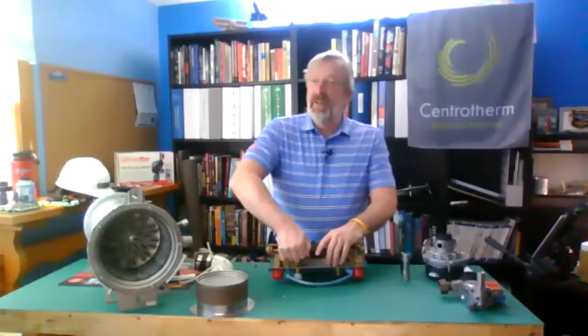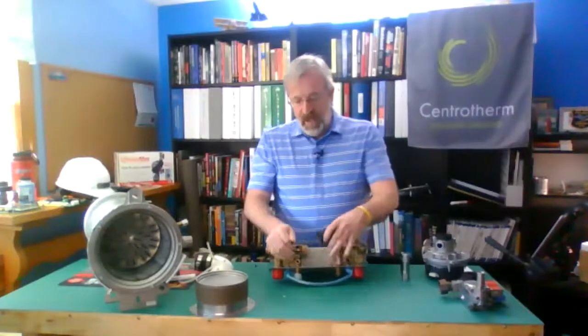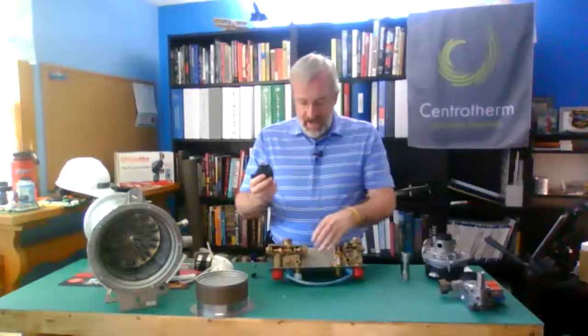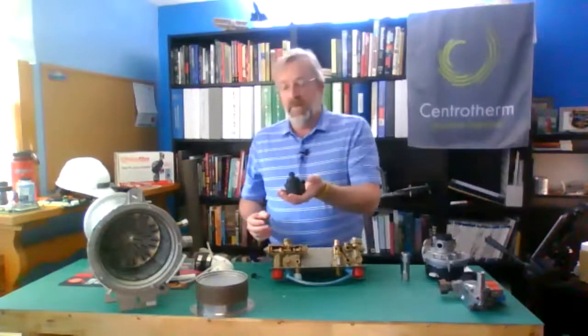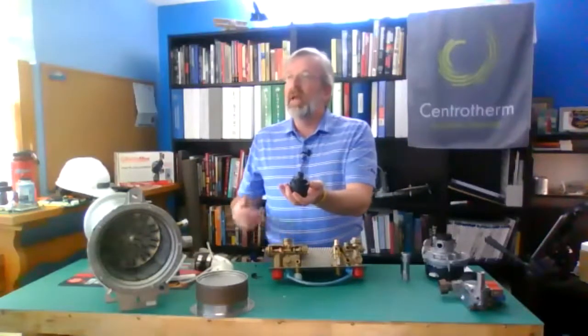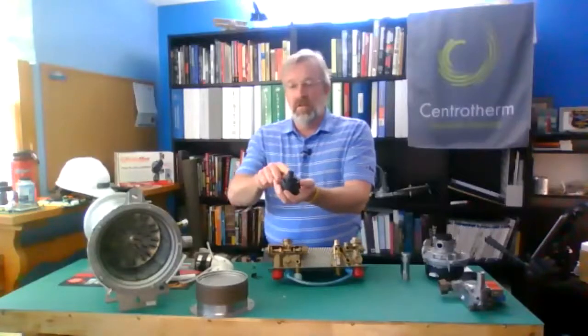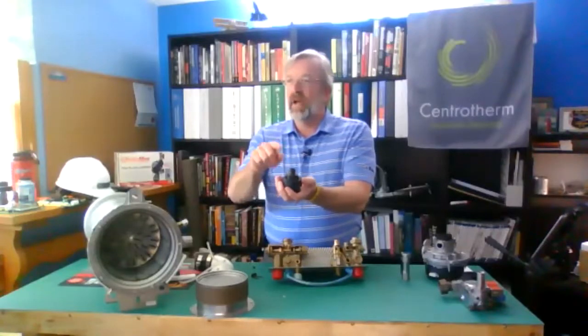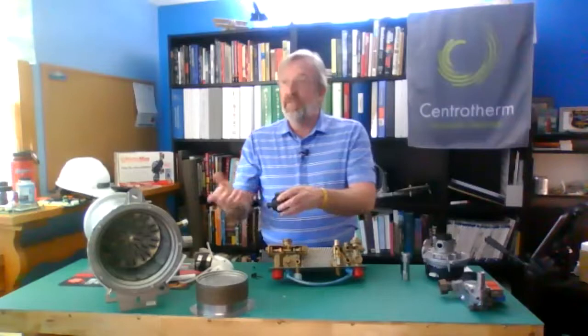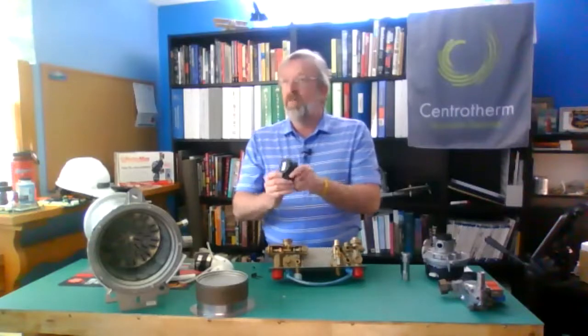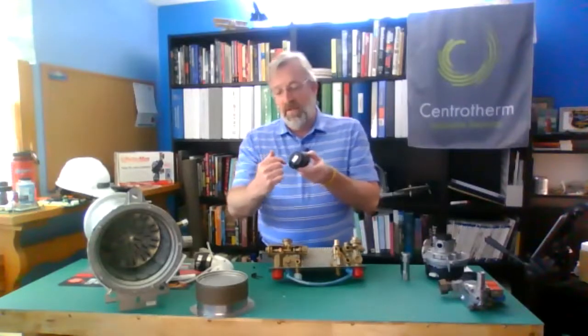If I'm concerned if it's working right, I've got this little clip here. By removing it, the diverter head comes out. Now, good news is you won't get wet when you take this off, so not to worry about that. If I'm not certain, hold this in your hand, make a domestic hot water call. You'll watch it divert right there. It's a great way to see it. If it doesn't divert, same way we checked that other fitting, we've got a Molex plug here. Let's check for 24 volts right there.